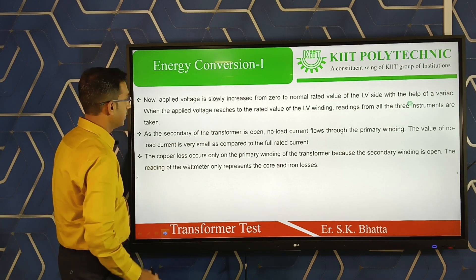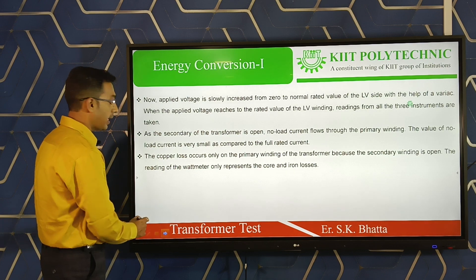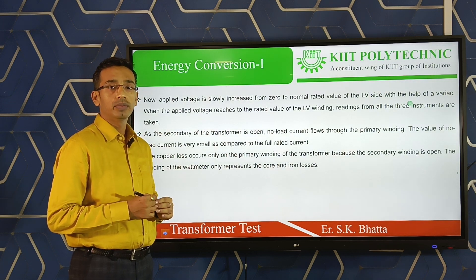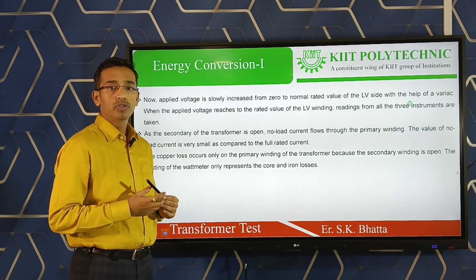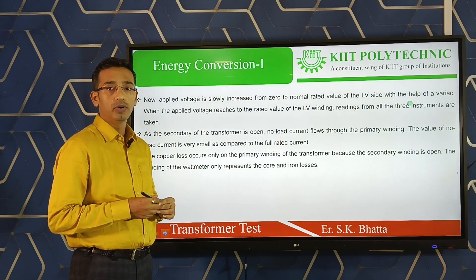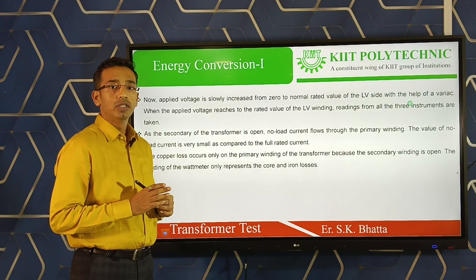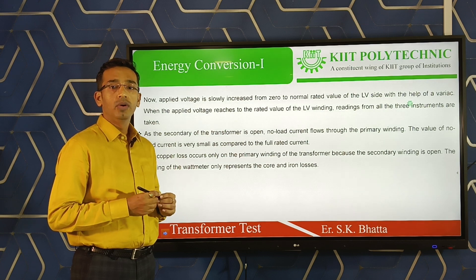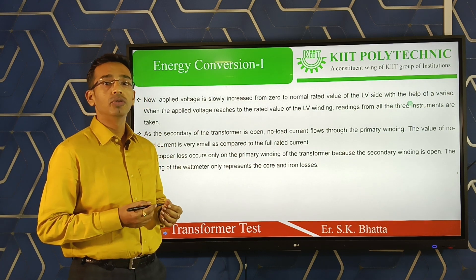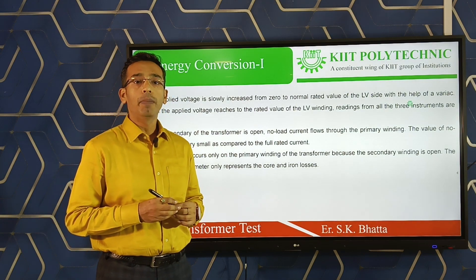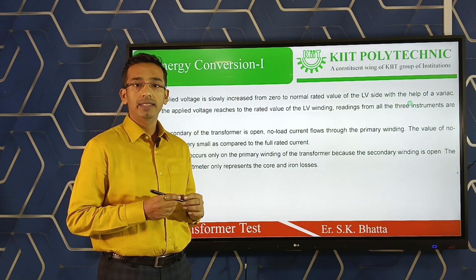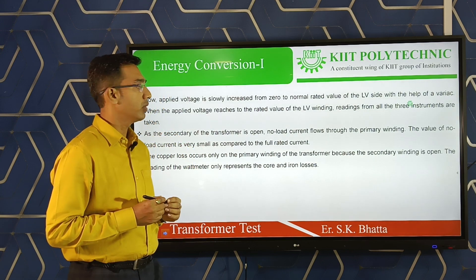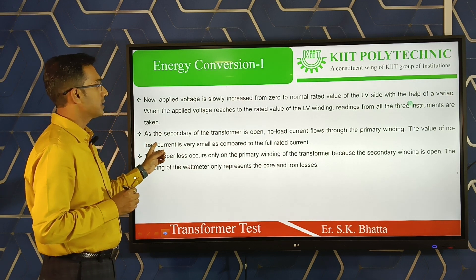For conducting the test, rated voltage is applied through a variac — an auto-transformer that varies the voltage. We vary the voltage up to the rated value and then take readings: the ammeter reading gives current, the voltmeter gives voltage, and the wattmeter gives power. The power reading from the wattmeter in the open circuit test represents the iron loss of the transformer.